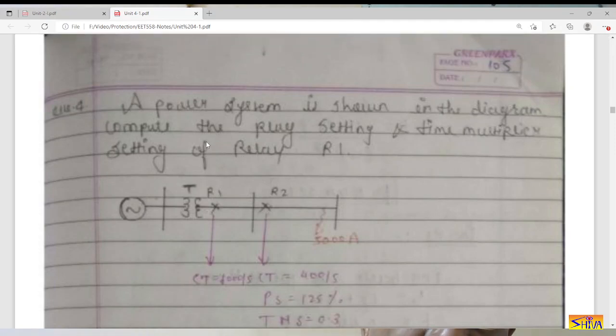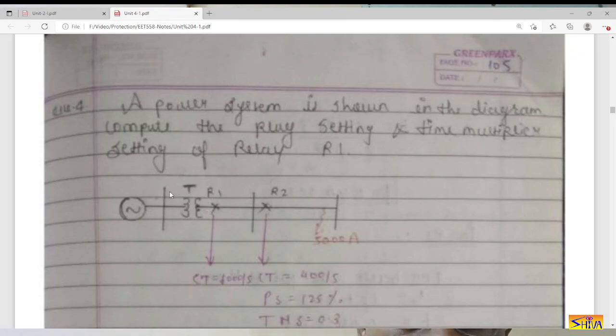The numerical is: a power system is shown in the diagram. Compute the relay setting — that is plug setting and time multiplier setting — of relay R1. There are two line sections with an incoming line and a step-down transformer, since these are distribution lines. The first line is protected by relay R1 and the second line by relay R2. At the end of the second line, a fault is given with a fault current of 5000 amperes.